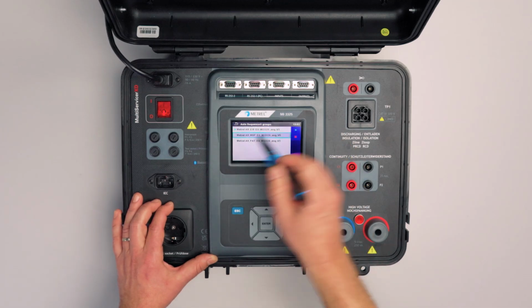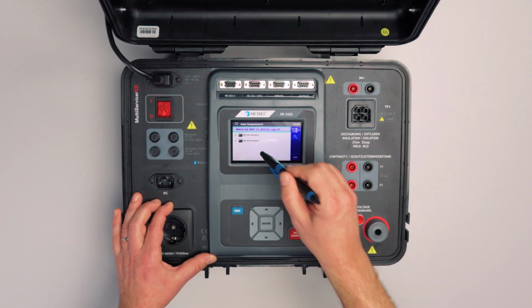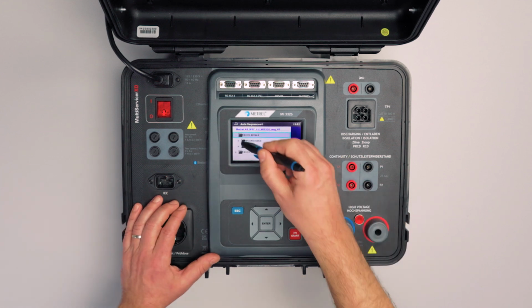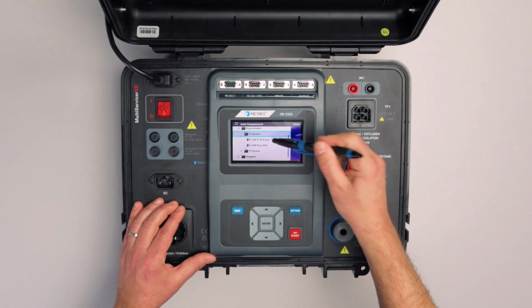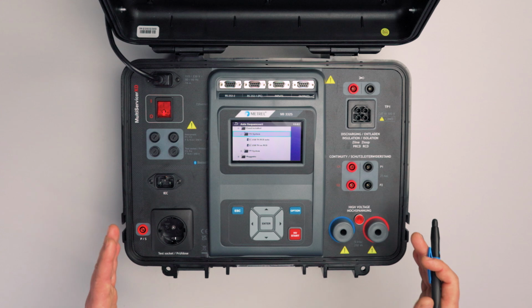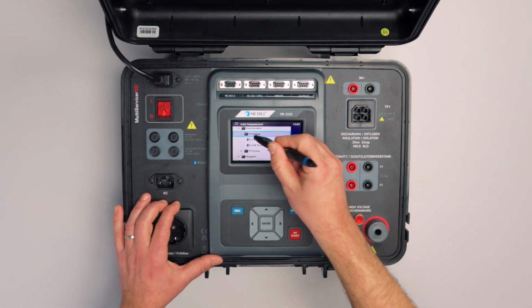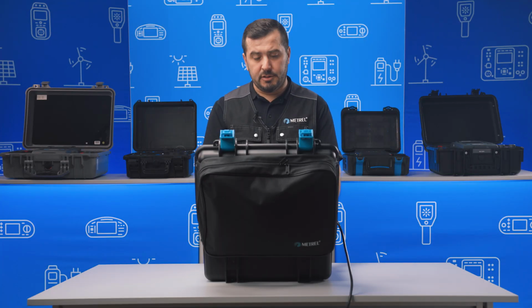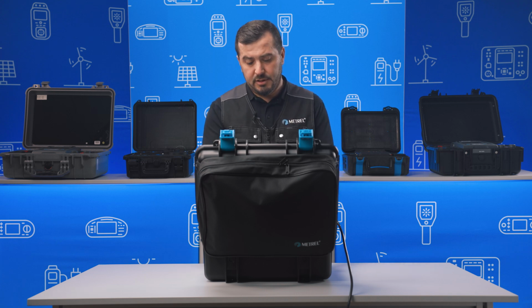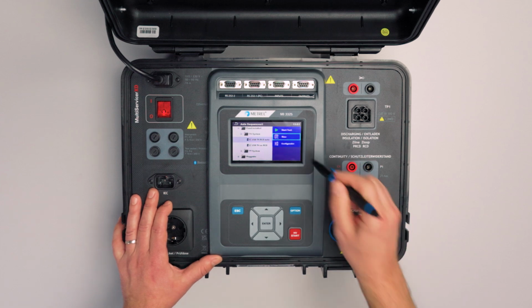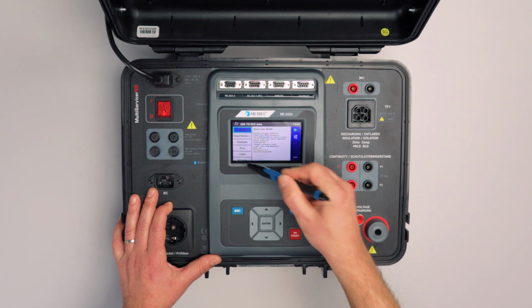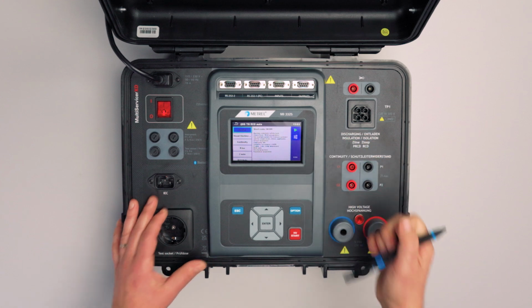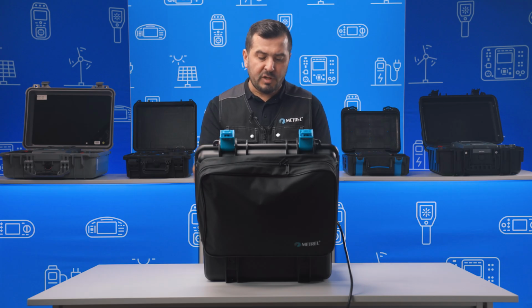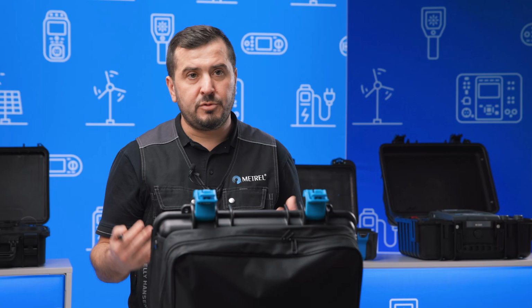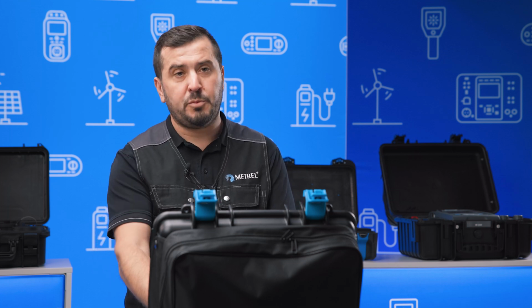If we now select a different group, for example, like this, the instrument automatically jumps back into the auto sequence menu, and now we can toggle here between these auto sequences, which can be organized in a folder tree structure. And of course this is up to the customers. They can decide how to organize this data. The parameters of each specific auto sequence can also be edited before the auto sequence is executed. So here on the right side we can choose the option View, which will show us all the measurement steps of this auto sequence. And of course, if the auto sequence was created in a way that there is an explanation or some text or some notice, we can also read for what purpose this auto sequence was made.